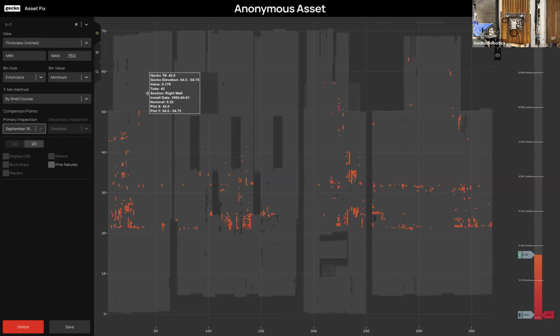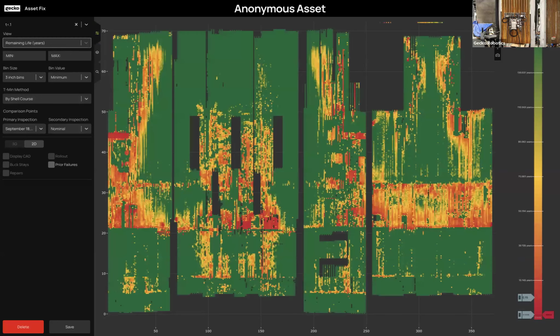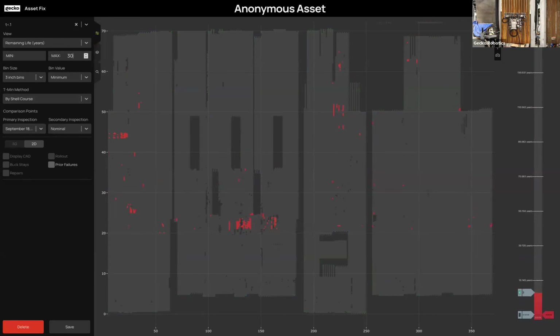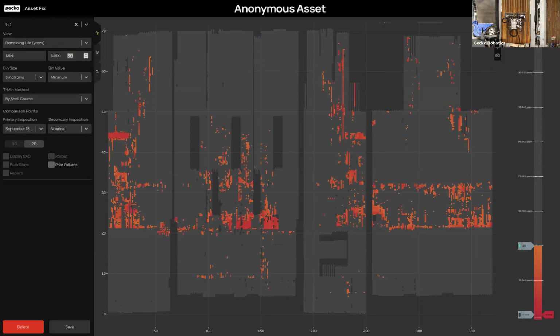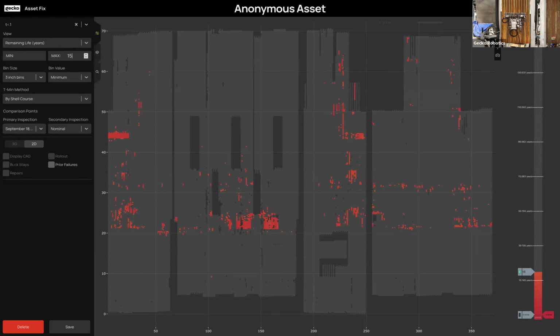So part of what we do here is take into account the differing rates of wear, so we can look at how much life is left in every tube. This is that answer across the whole boiler. If you want to operate the boiler for 30 years, here are the areas that may be concerning, or if it's 15 years, there's that.